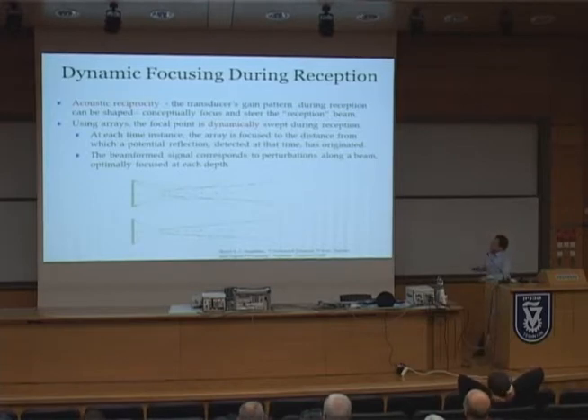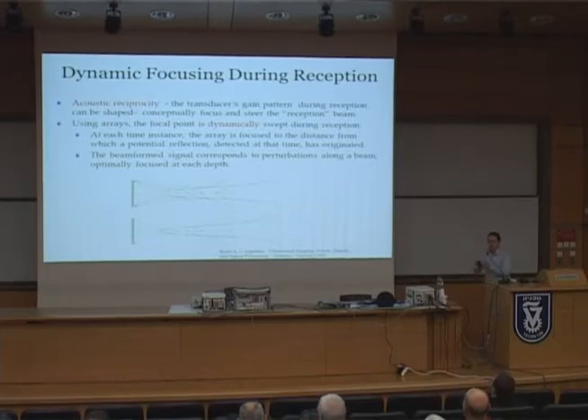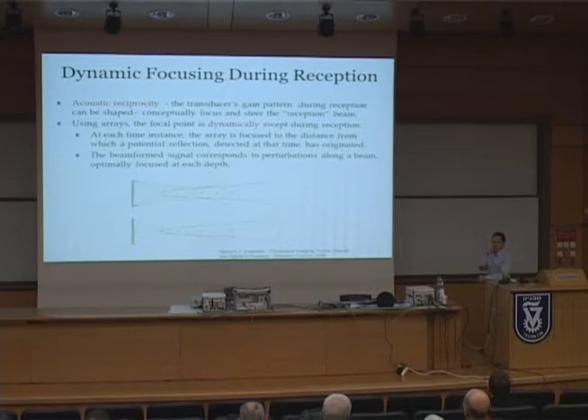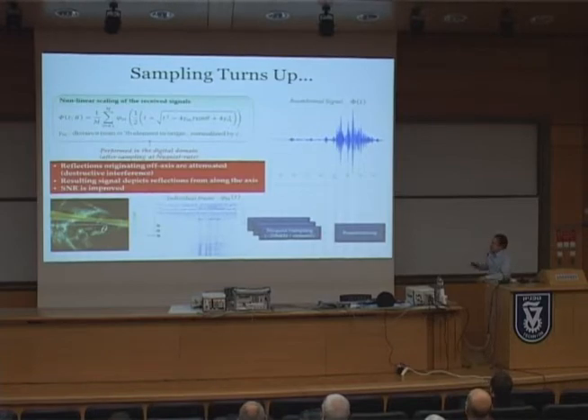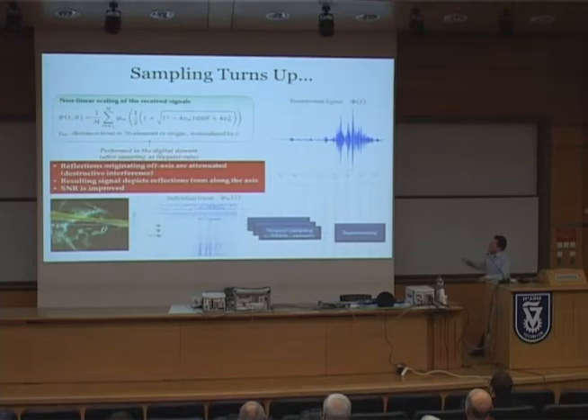Using arrays, we have the ability to change the focal point over time. We can exploit the straightforward relationship between detection time and perturbation distance to sweep the focal point through time, obtaining a beam optimally focused at each depth. This is more or less where sampling comes in, because this whole dynamic focusing calculation is done in the digital domain by modern devices. Here we have the equation for this dynamic focusing, or beamforming.